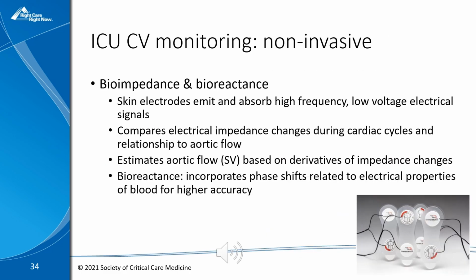Bioimpedance and bioreactance are non-invasive measurements of stroke volume and cardiac output. These technologies use electrodes that are placed on the skin. These electrodes emit and absorb high frequency but low voltage electrical signals and compare the impedance characteristics at 4 points on the patient during cardiac cycles and make a relationship between those impedance changes and aortic blood flow. Thus, these monitors are able to estimate the aortic blood flow, that is, the stroke volume, based on derivatives of the impedance changes. The Cheetah Starling SV system uses bioreactance, which incorporates phase shifts related to the electrical properties of blood to achieve higher accuracy.